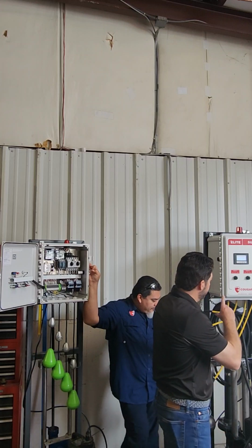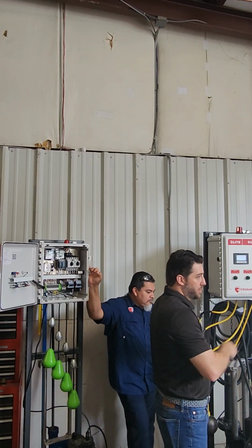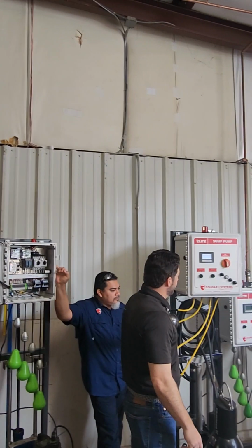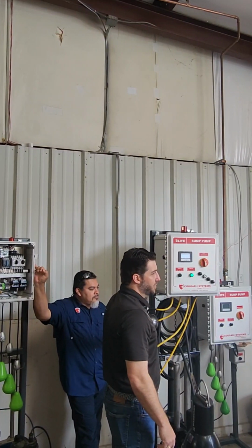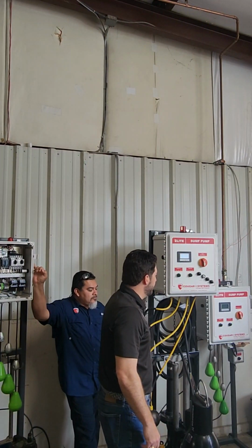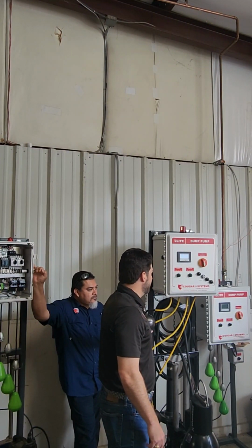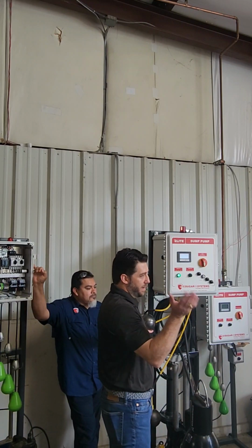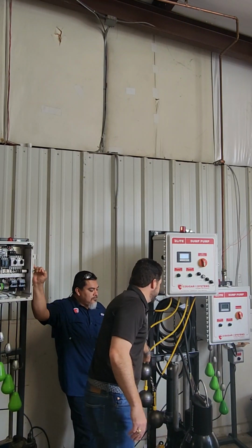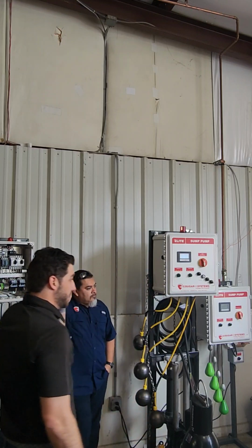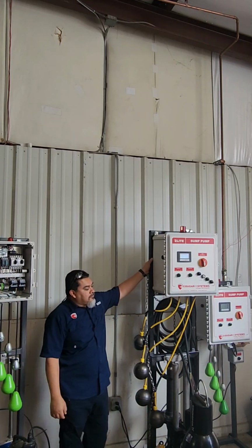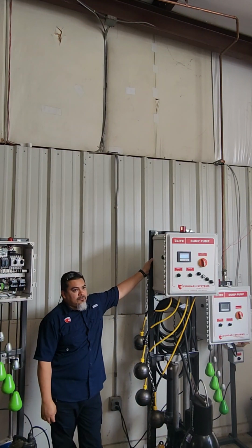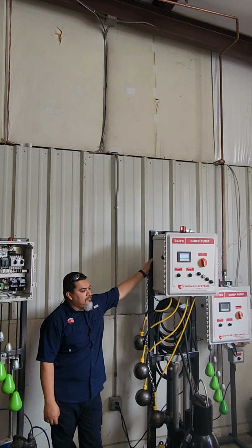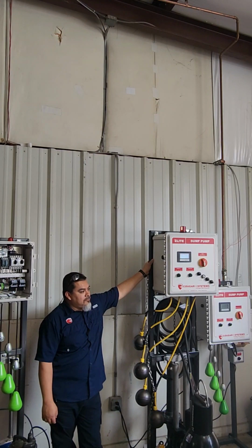Like if we're in a two-float system, if we're using one float to turn the pump on and off, we have an on delay with the float switch, right? Yeah. So it takes a little time for it to turn on, so that way it's not bouncing. Those time delays are built into the system. It's just to make sure it doesn't barely turn on and then go off. It's like making sure it's up before it turns on.